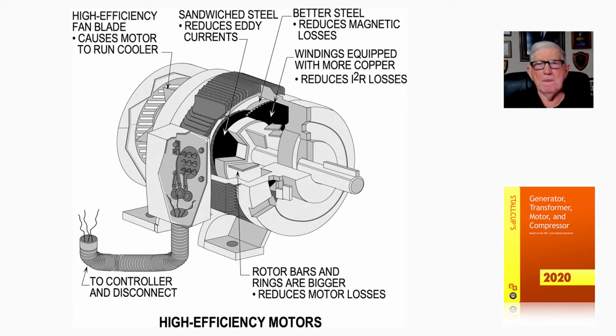Now, as a rule of thumb, I've been told that if you buy a high efficiency motor that really doesn't pay you back as fast using it and purchasing it, it starts at about 8.5 times the nameplate current. If you bought the next, it'd be 10, then 12, and 15. So that's why the code would go up to 1,700% to let this motor start and drive its load. But it's a high efficiency motor that doesn't pull as much current-wise, that would cause the bill to be higher for running it. So it's just a high efficiency type motor that many of our manufacturers manufacture for if someone wants to purchase it and use it.